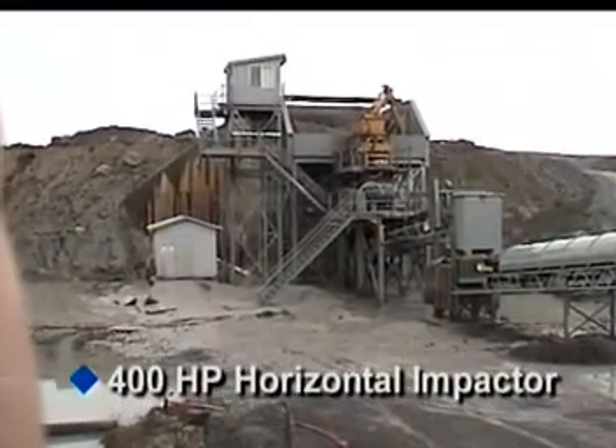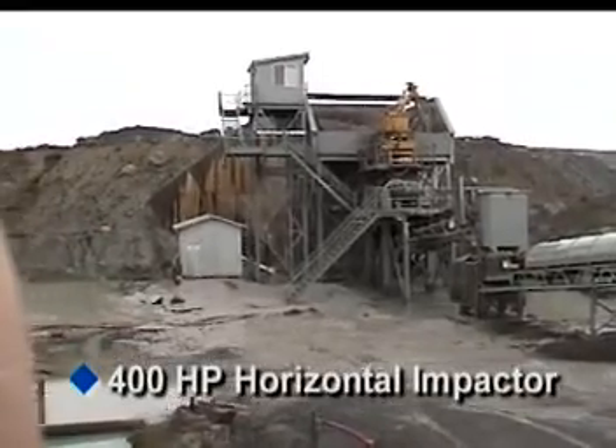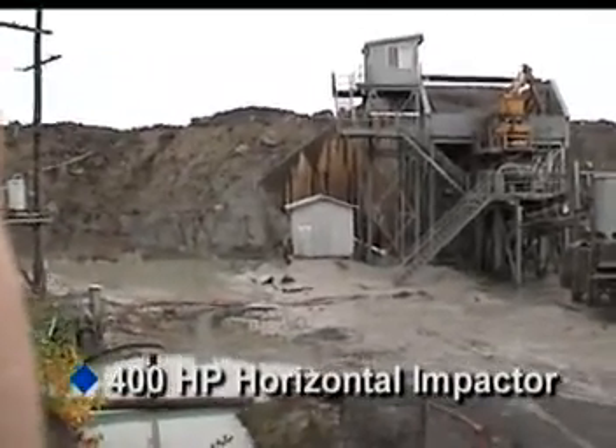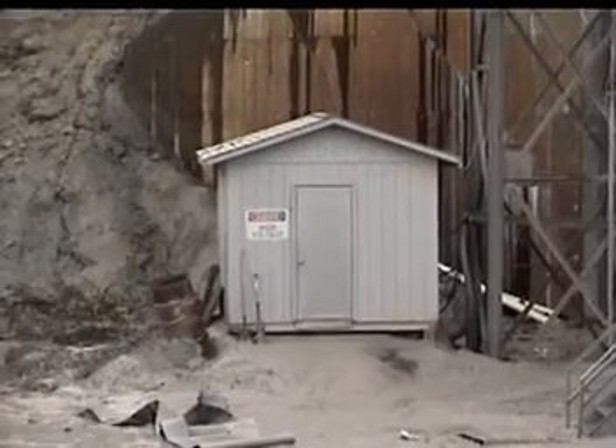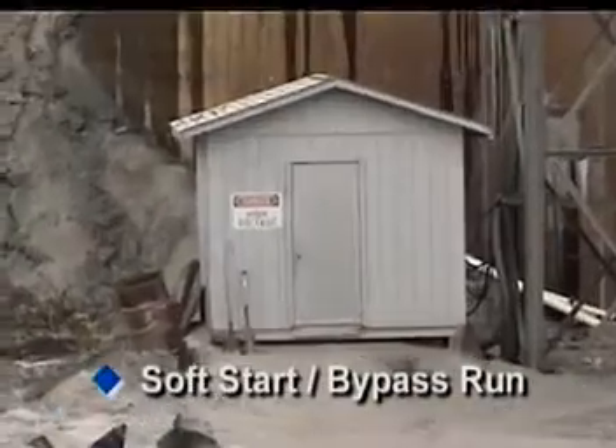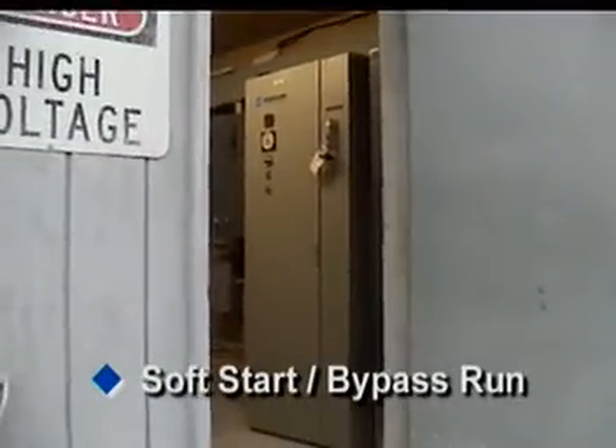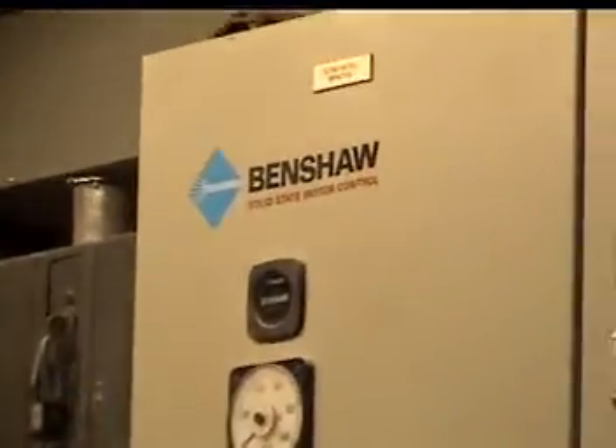Shown here is a 54 by 48 inch horizontal shaft impactor driven by a 400 horsepower induction motor, which is controlled by a Benshaw combination NEMA 12 solid-state soft start crusher control package.